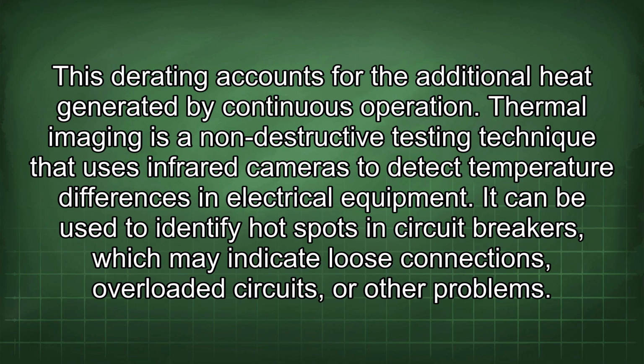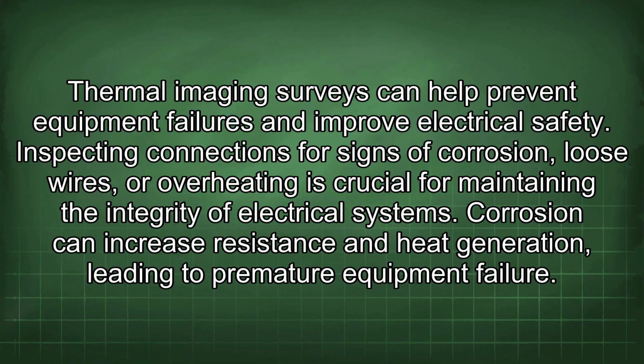Thermal imaging is a non-destructive testing technique that uses infrared cameras to detect temperature differences in electrical equipment. It can be used to identify hotspots in circuit breakers, which may indicate loose connections, overloaded circuits, or other problems. Thermal imaging surveys can help prevent equipment failures and improve electrical safety.